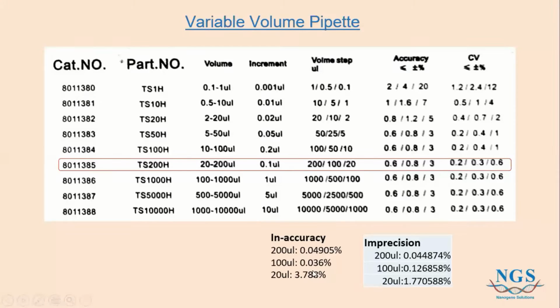All right, so let's move on to the smallest volume that I'm checking. So it's 3.788%. And in my table, it says that everything should be right if it's within 3 to negative 3%. Yeah, so it is actually out of the range. It's a bit higher, right? It's 0.788% higher. So unfortunately, our pipette is out of the range. All right, so that kind of indicates that you might need to calibrate your pipette, and your pipette might not be working the best that it's working.